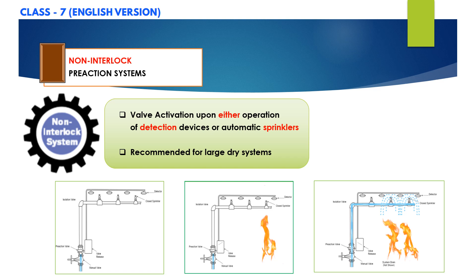Non-interlock type is recommended for large dry systems which exceed the capacity normally permitted on a dry valve by NFPA 13. There is a limitation for maximum capacity for dry pipe systems. If you want to know more on dry type systems, you can check the related video for more details.